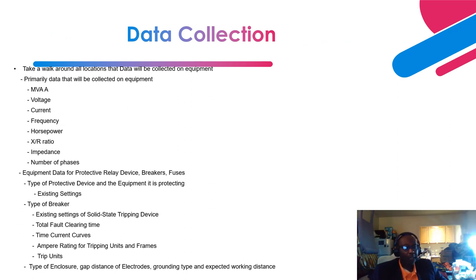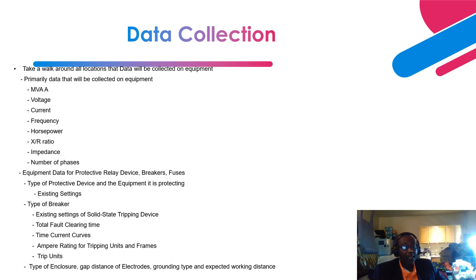Now let's talk about data collection itself. In general, the typical parameters that need to be collected on equipment include: MVA rating, voltage rating, current rating, frequency, horsepower rating, X/R ratio, impedance, and number of phases — since you may encounter single-phase or three-phase equipment. For protective relay devices, breakers, and fuses, the existing settings are very important. For breakers, you can obtain existing settings for the solid-state tripping device, the total fault clearing time — which may be two, three, five, or eight cycles — the operating mechanism for the tripping unit, and the frame size, especially for low-voltage power breakers.